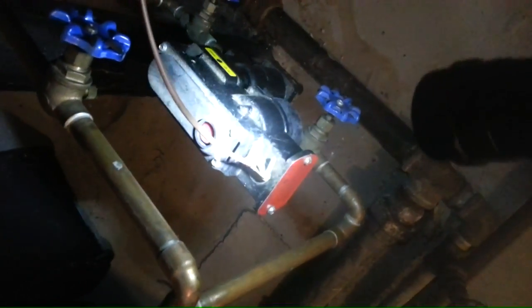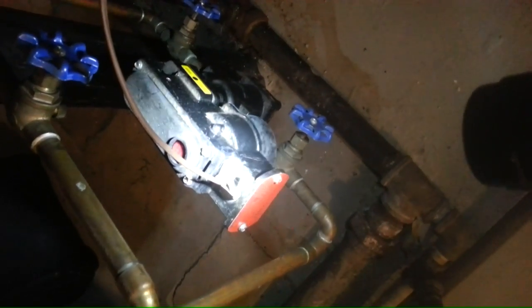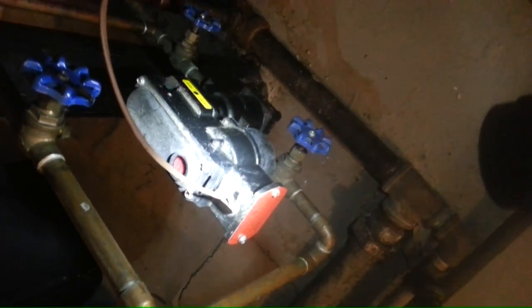Now we're going to cycle the power. This can happen by a storm, or it could happen by an electrician working on the house, or anything. Now the low water cutoff is in a delay-on-make mode — it's trying to figure out what it's doing when the power is first turned on. Look at the button on the feeder, it's down now. It's feeding water into the boiler, and the boiler is going to flood.